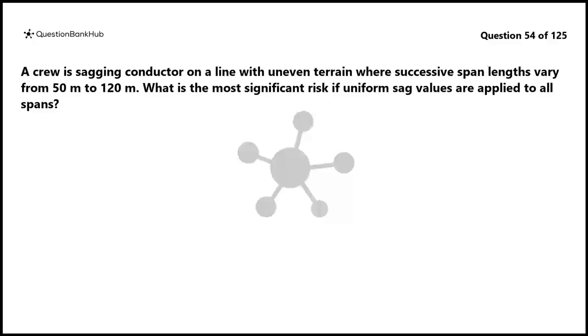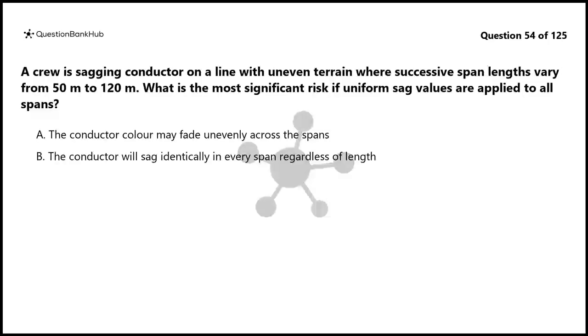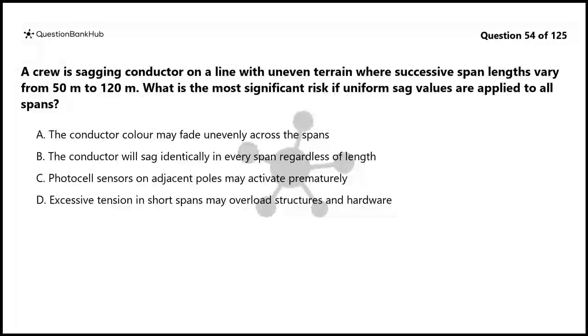Question 54. A crew is sagging conductor on a line with uneven terrain where successive span lengths vary from 50 meters to 120 meters. What is the most significant risk if uniform sag values are applied to all spans? A. The conductor color may fade unevenly across the spans. B. The conductor will sag identically in every span regardless of length. C. Photocell sensors on adjacent poles may activate prematurely. D. Excessive tension in short spans may overload structures and hardware.